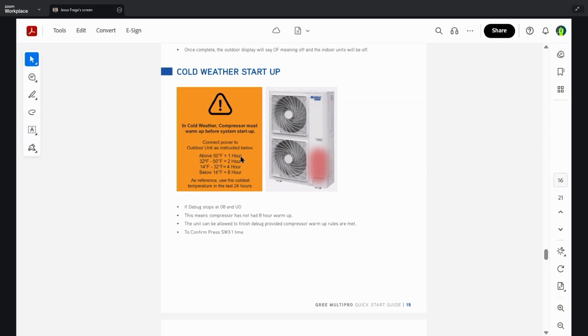So we know that anything above 50 degrees is going to be a 1-hour warm-up period. Anything between 32 and 50 is going to be a 2-hour. Anything between 14 and 32 is going to be a 4-hour. And anything below 14 is going to recommend that 8-hour warm-up period. This is to ensure, as I stated earlier, that the compressor lasts as long as possible. Failure to follow this will result in catastrophic compressor failures. Maybe not initially, but prematurely.